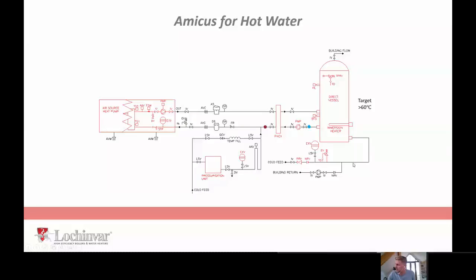Our building return comes back at 55. Flows into the base of the cylinder, blends with our cold feed as well if there's a demand on the building, floods through the plate heat exchanger again, circulates through, back at 62 degrees centigrade. So on this side of the system, we're at 62, 58, something like that. That's not 5, is it? 62, 57. And on this side of the system, we're working 63, 58, so 1 degree higher than the secondary. This is the same principle you'd employ if you were doing a heat pump retrofitted onto a dirty system, and they were the sort of temperatures you were looking for. Except that would be your building flow, that would be your return, but there would be no outlets. Okay, and then it's just a case of making sure that that pump is spec'd to match the same flow as this pump here, and that way you know that you're putting into the plate exactly what you're getting out.